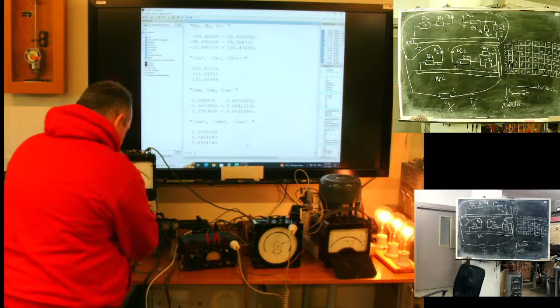That's why a negative sequence relay or negative sequence trip function should be used. Voltage asymmetry protection will not work. In this case, without resistance, we have quite significant voltage asymmetry. But transient resistance lowers it. Asymmetry is not so big. Okay, I assume it's enough for today.